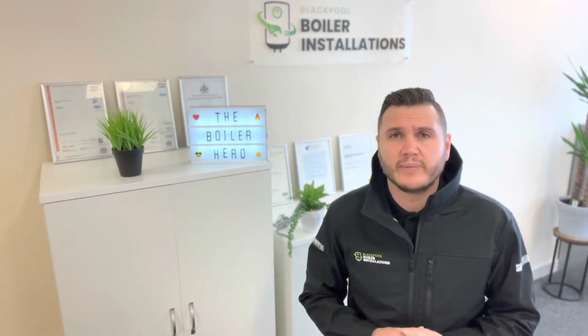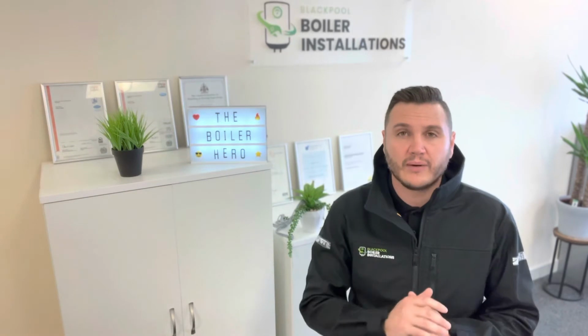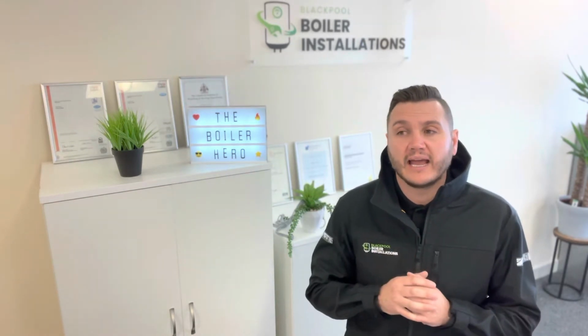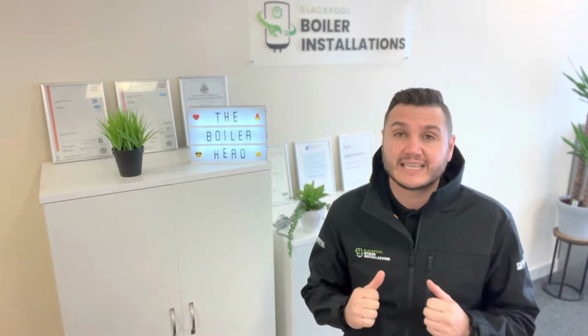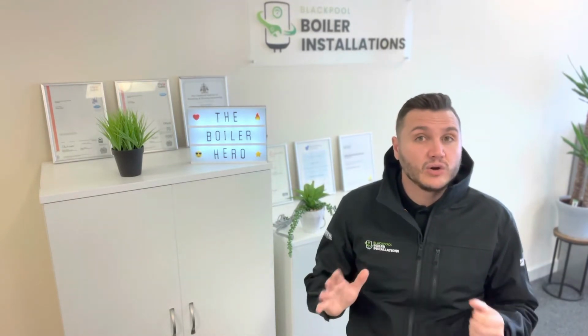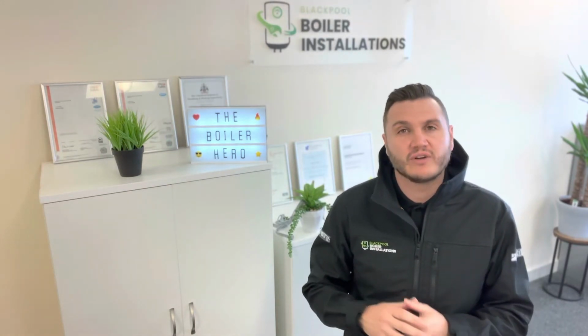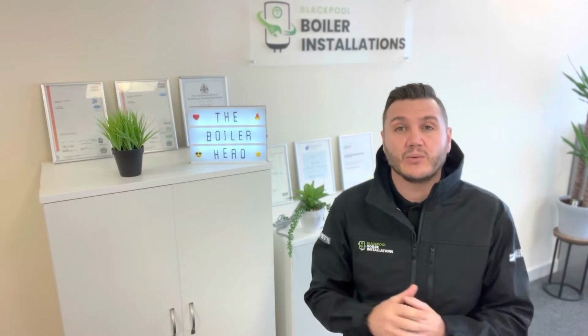Number one is there could be a small leak on the boiler. So give us a call, we will come out and check our work. If there's a problem with anything we've done on the boiler or near the boiler, we will fix that, obviously free of charge, because you've already paid for us to fit your new boiler. Okay, it could mean that you've got a leak somewhere else on the system that you might not have known you'd had before, but since you've got a new boiler, this boiler's telling you about it.